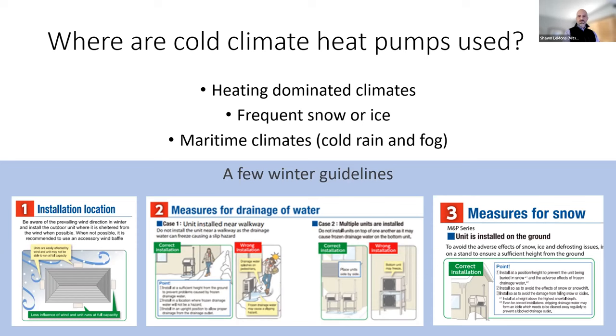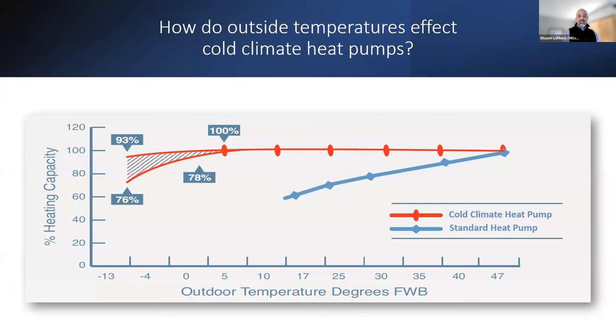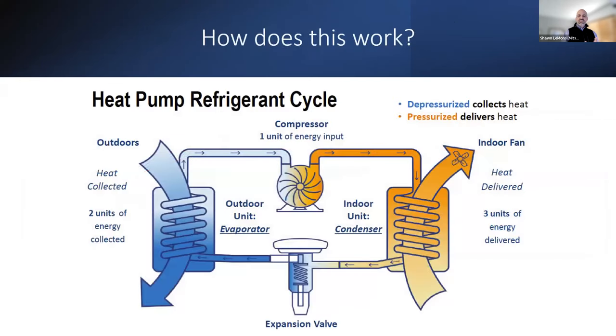All considerations for good cold climate guidelines. And then looking at this chart, it's a pretty simplified chart, but it does get the point across: a standard heat pump in the blue line there versus a cold climate heat pump with the red line. And that red line, from our perspective, for our manufacturers, we're looking at 100% capacity at 5 degrees and starting to stretch into those negative numbers on full capacity. And then that tapering off and that broadening range there at the left side really depends on the model that you're talking about. You know, the good, better, best, the features that it comes with, which model are you looking at? Sorry, now, Sean, can I jump in on it?